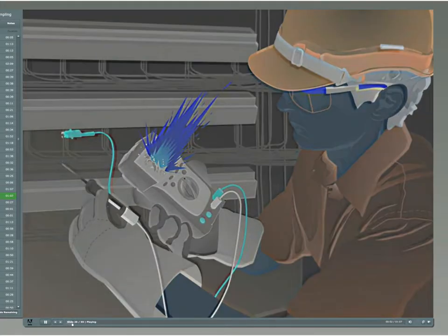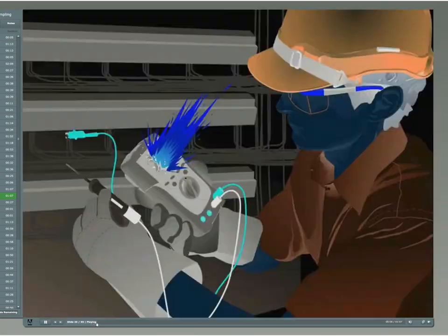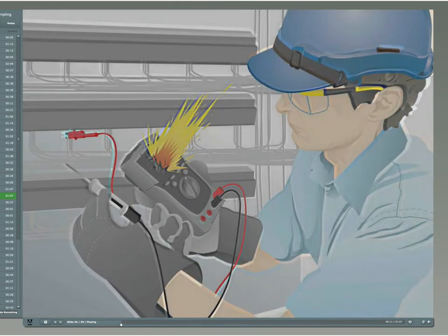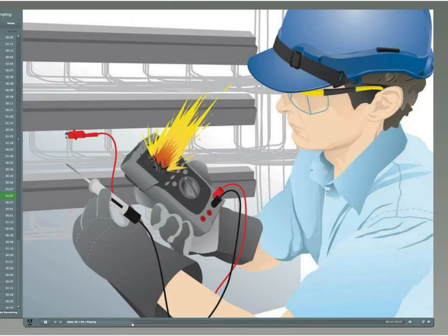You touch the test leads, which are still connected to the current terminals on the meter, to the voltage buses. A direct short across the source voltage occurs inside the handheld multimeter through a low-value resistor. A very high current will flow through the test leads and the meter. If you were working in an area with very low circuit impedance, this fault current can be thousands of amperes, or even tens of thousands of amperes. The test leads and the meter circuitry are not designed to handle such a high current. The test lead or the meter will cause an open circuit.